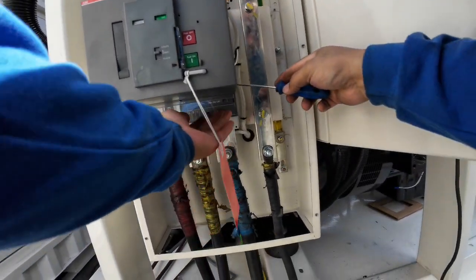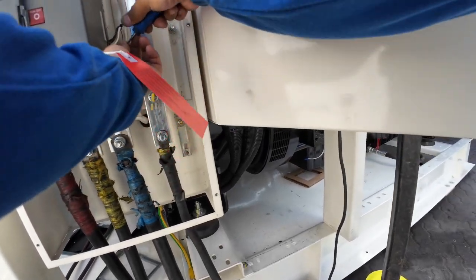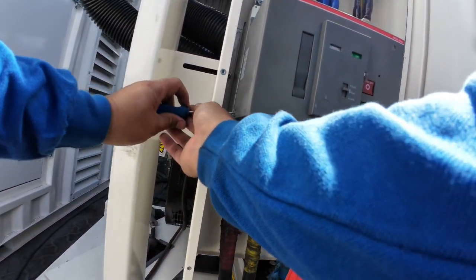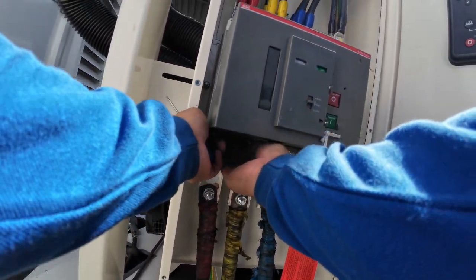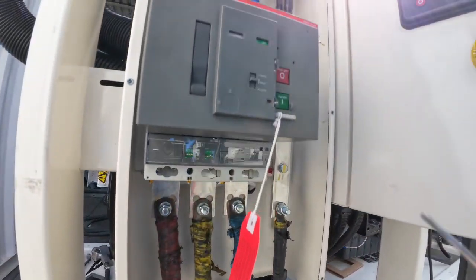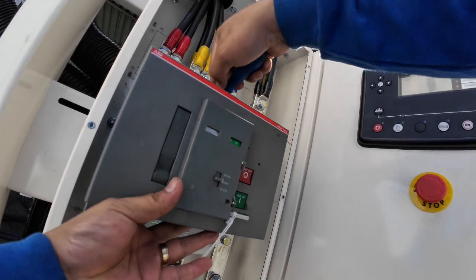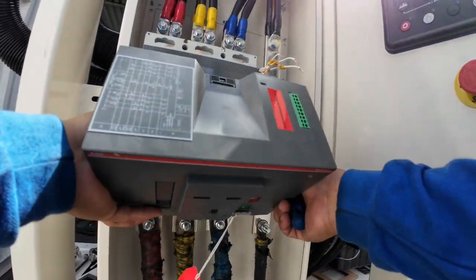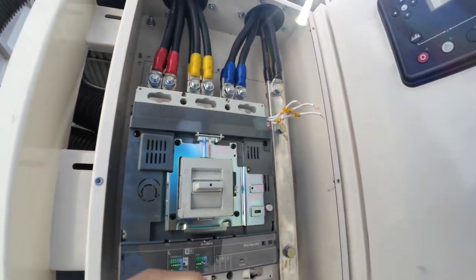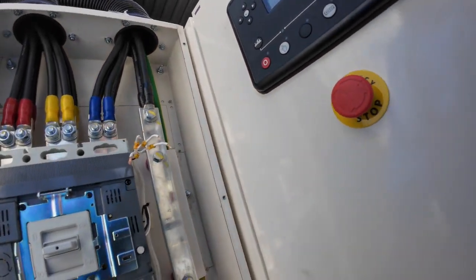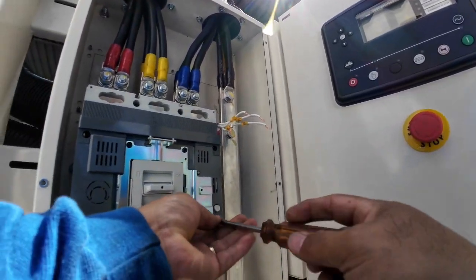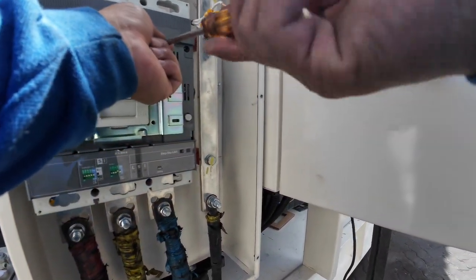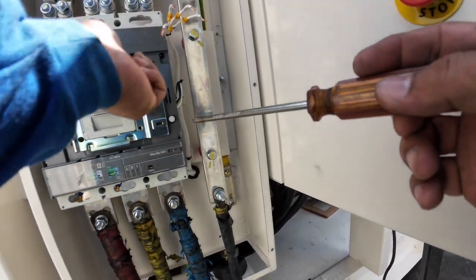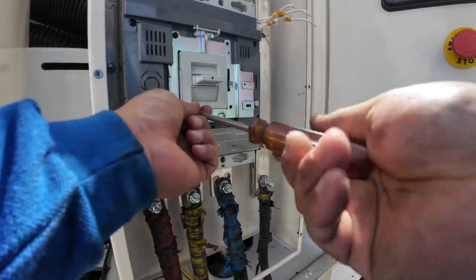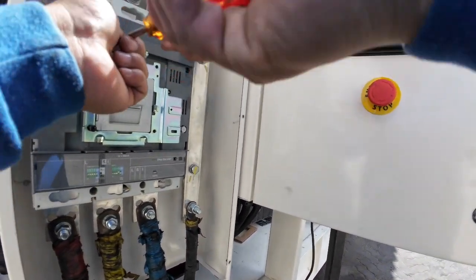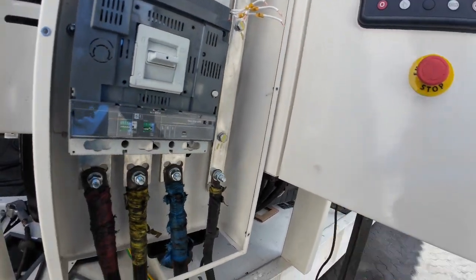And make sure you are in the manual setting on the breaker, so you can open it, because if you are in auto, you cannot open it. Even if you force it, maybe it will break the knob inside, so it makes you a problem. It's as simple as that to remove this motorized head cover, and now we are at the breaker itself, so we can see the connections from inside if they are correct. Just follow how I remove the bolts and the screws, so you can also remove your breaker. Just look and observe how I open it.